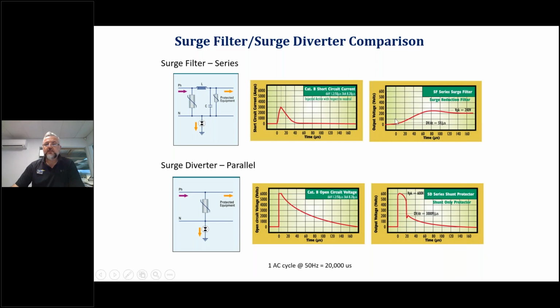And one of the main things is that you can't see here this fast rise time of voltage. And this fast rise time of voltage, which a surge diverter can't do anything about, is what normally kills CPUs or sensitive electronic equipment. So if you want to protect your electronic equipment, whether it be the touchscreen on your EV charger or any display or anything like that, you should consider surge protection, either a diverter or a filter. But as I said earlier, this is all optional, and you can request that from your EV supplier.